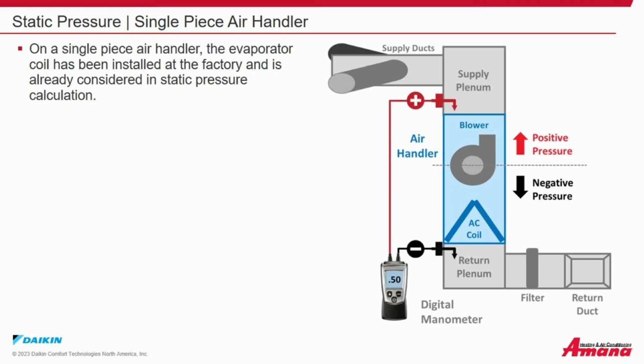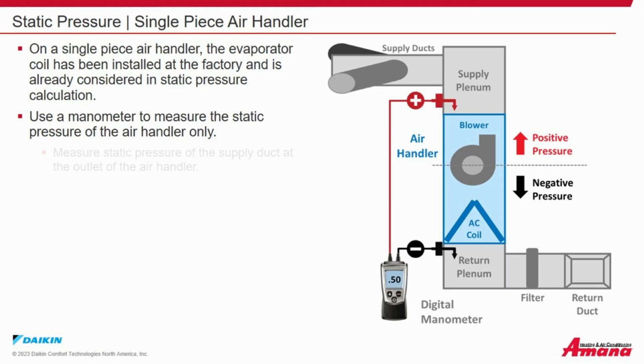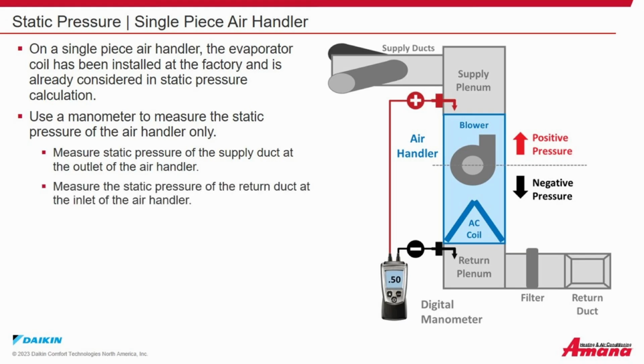Static pressure, single-piece air handler. On a single-piece air handler, the evaporator coil has been installed at the factory and is already considered in the static pressure calculation. Use a manometer to measure the static pressure of the air handler only. Measure static pressure of the supply duct at the outlet of the air handler. Measure the static pressure of the return duct at the duct inlet of the air handler.